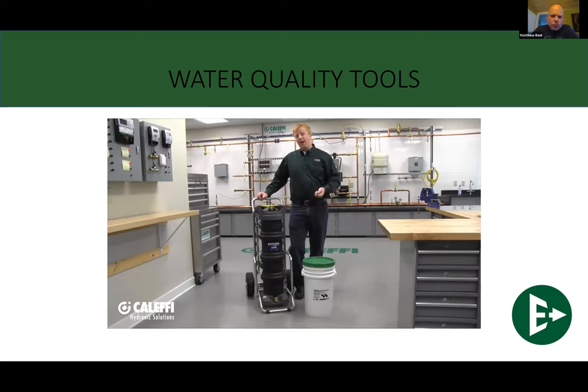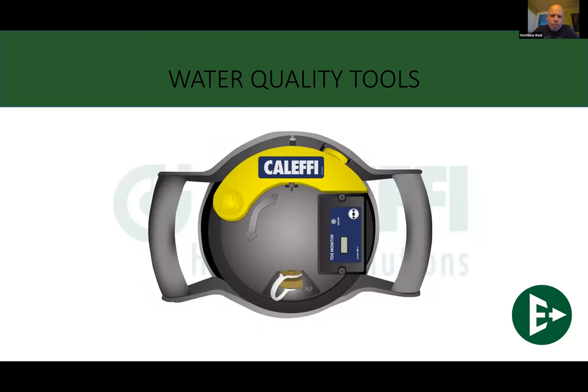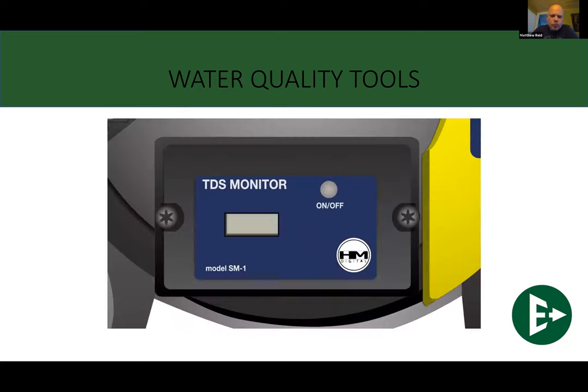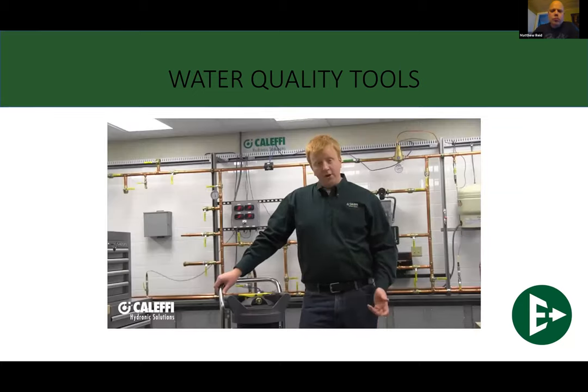So again, you've got your hoses connected and you're filling up your system. You are going to want to make sure to keep an eye on that TDS meter that's on the very top. When you start filling the system, you're going to see roughly about 0 parts per million, maybe up to 10 parts per million. As the resin bags start to get depleted, then you are going to start seeing it creep up a little higher and a little higher. At 30 parts per million, we do recommend changing out the resin bags. So let me show you how to do that. First, you're going to want to shut off your site water supply, wherever you're getting that from.